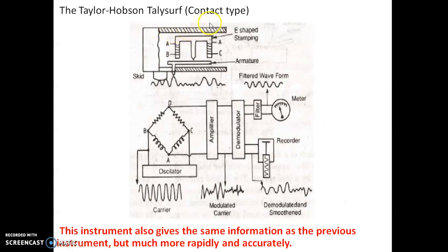The Taylor Hobson Talysurf also works on the same principle. It consists of a probe connected to the armature. When the probe containing the skid moves over the surface, it moves up and down, and the motion is converted into an electrical signal. Digital electronics techniques are used to convert this signal into the surface roughness measure.